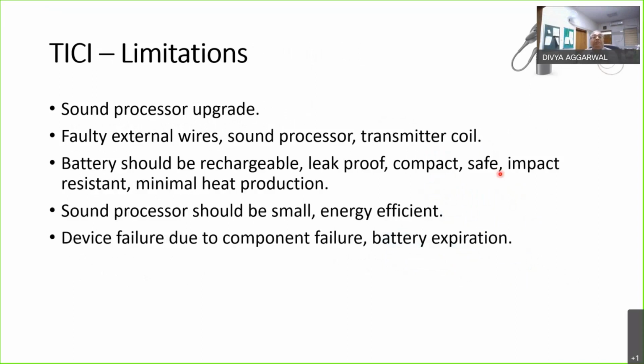Then, faulty external wire. If the external wire goes faulty, or the sound processor becomes faulty, or the transmitter coil becomes faulty, then again you will be in trouble, because you will have to take it out, get it repaired, and surgically place it back. Then the battery should be rechargeable, leak-proof, compact, safe, impact-resistant, and with minimal heat production. The sound processor should be small so that it is not visible in the profile of the skull.